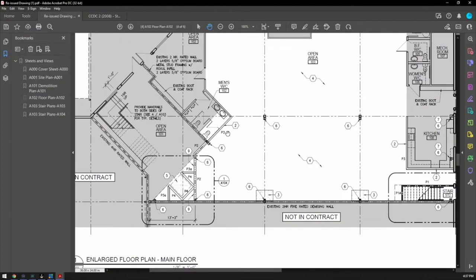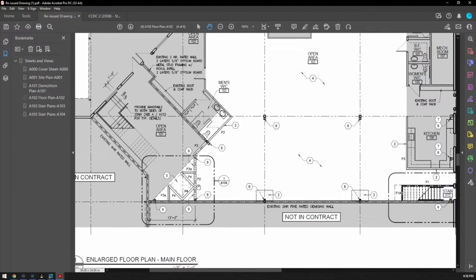You can see here. So P3, I picked blue for P3. I'm going to highlight P3 and I'm going to highlight all the different styles of walls. This is a P2. P2 is double layer five-eighths, both sides. This here is a four hour wall. This is actually a concrete masonry unit here. Oh no, up here is concrete masonry unit. So it changes.